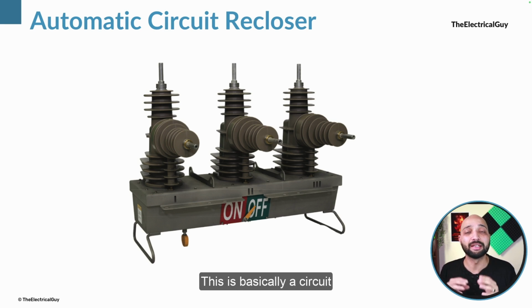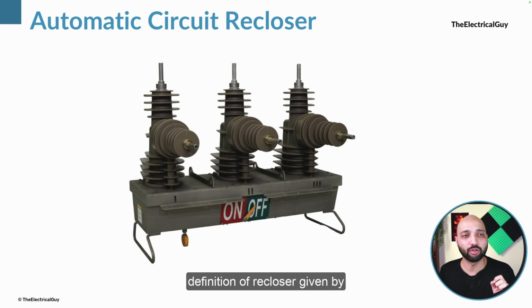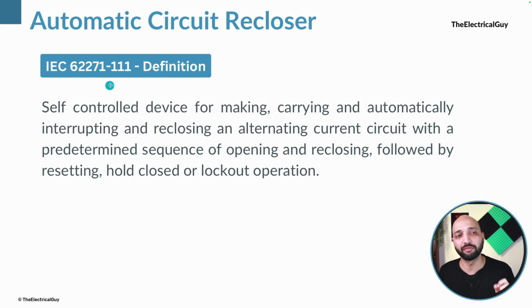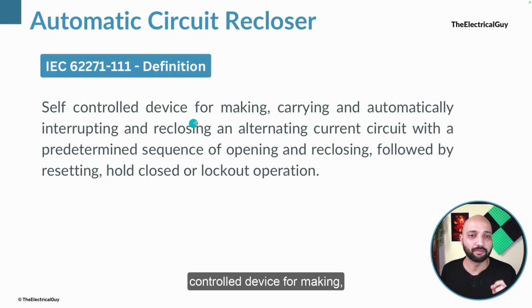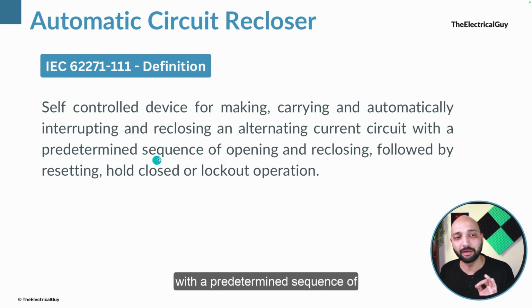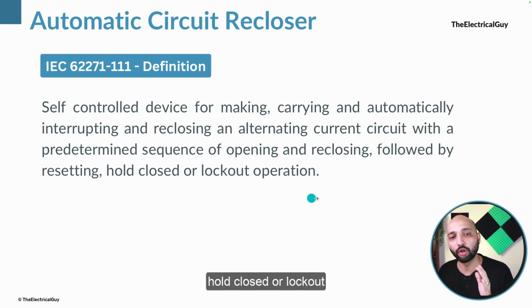This is basically a circuit breaker which has capabilities to sense the abnormal condition and open when needed and reclose when needed, right? In a simple language, this is the device, how it looks. Now, if we look at the proper definition of recloser given by IEC 62271-111, it says that it is a self-controlled device for making, carrying and automatically interrupting and reclosing an alternating current circuit with a predetermined sequence of opening and reclosing, followed by resetting, hold closed or lockout operation.